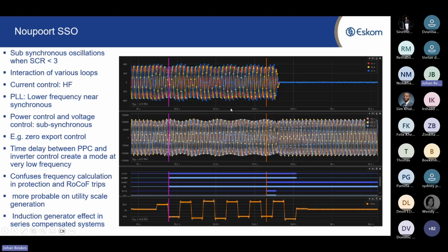So on one of our wind farms, we had a trip, and we looked at the protection relay, and there was a RoCoF relay that did its thing, and then we could get data from the RoCoF relay to see what happened. In this case, one of the transmission lines upstream tripped due to a snowstorm, and then the short circuit ratio of the wind farm dropped below 3.